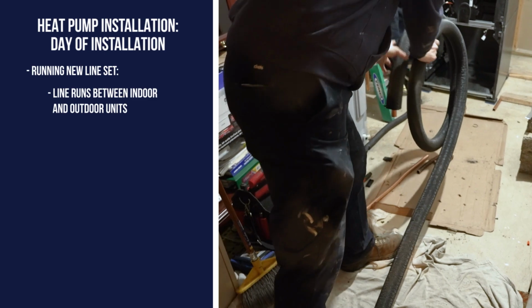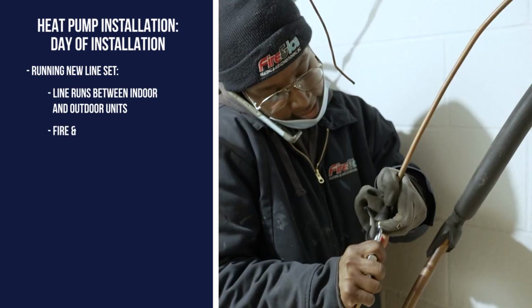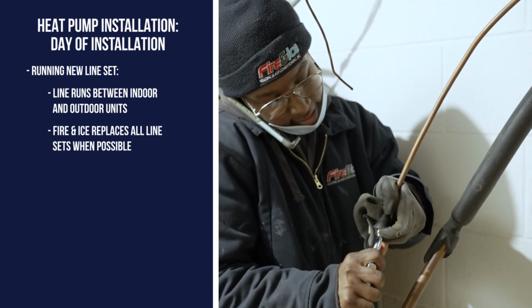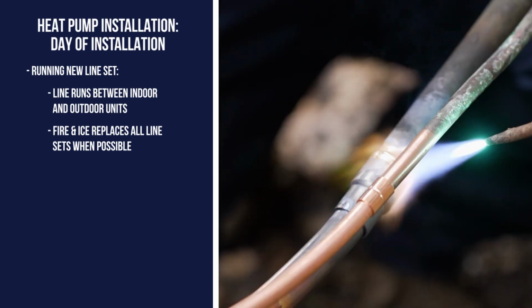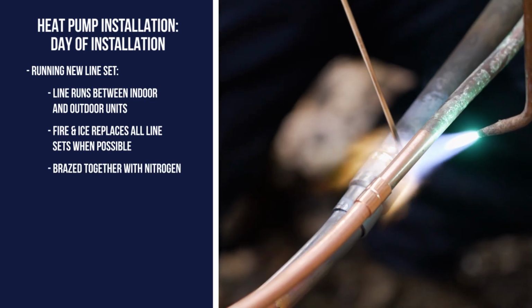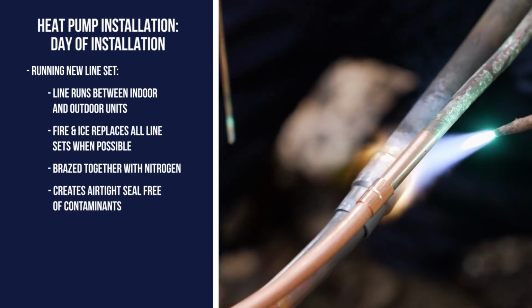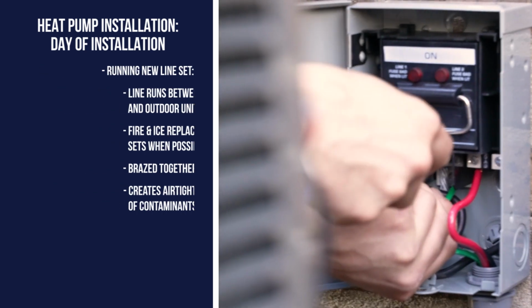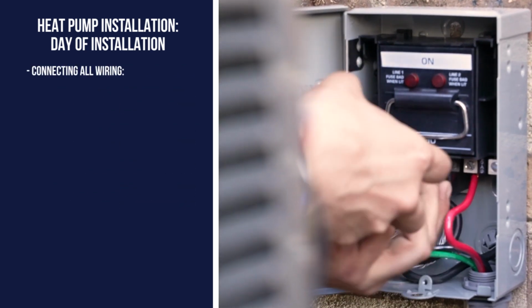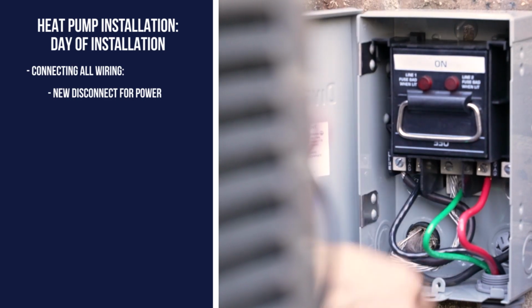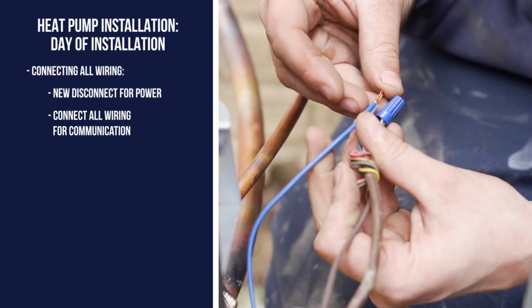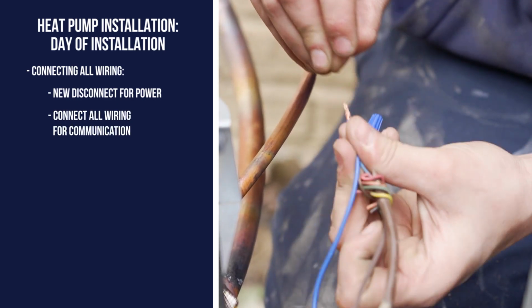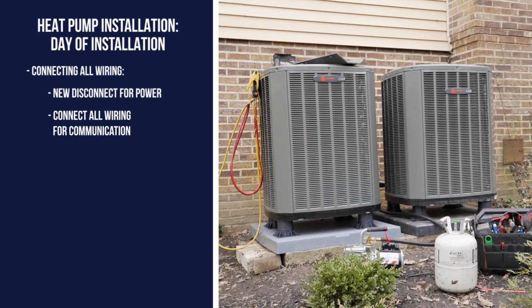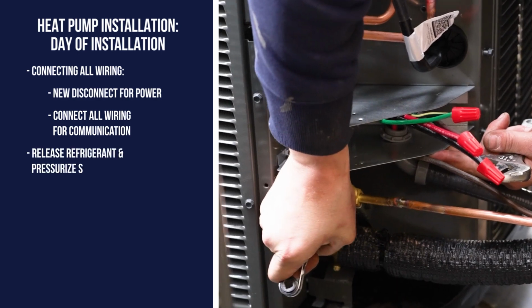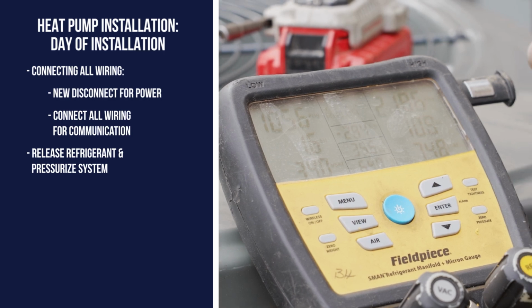Next, we run the new line set from the indoor unit to the outdoor unit and braze them together. At Fire and Ice, we replace all line sets and wiring when we're able to. The line set is connected by brazing it with nitrogen to create an airtight seal free of contaminants. The next step is connecting all the wiring. First is to install a new disconnect for power. Second is all the wiring needed for the heat pump to communicate with the rest of the HVAC system. After all the wiring is connected, it's time to release the refrigerant and pressurize the system.